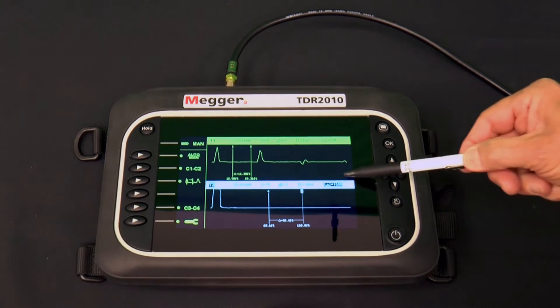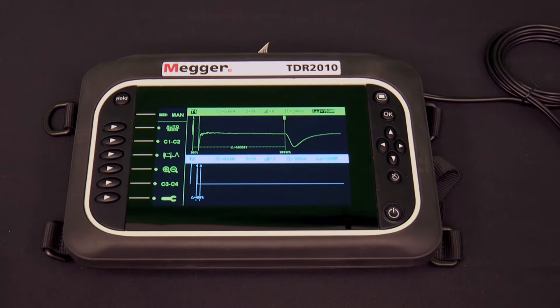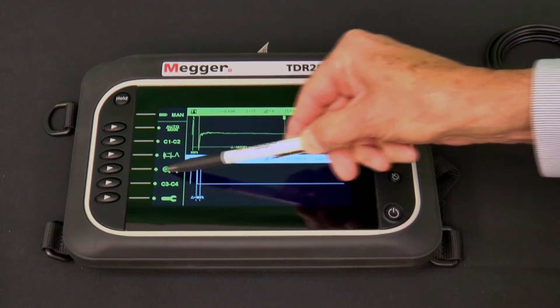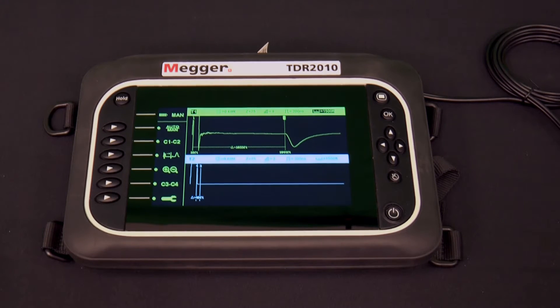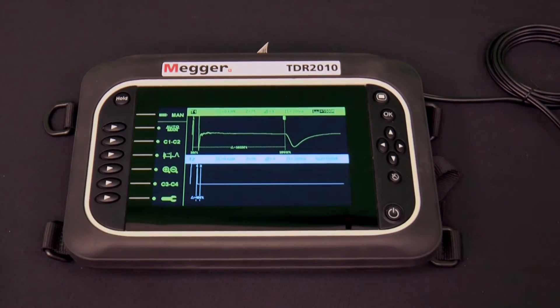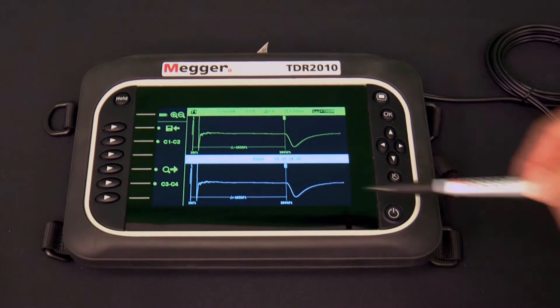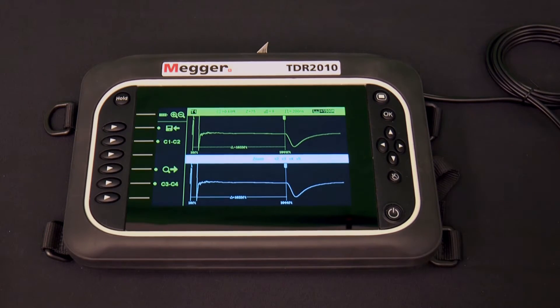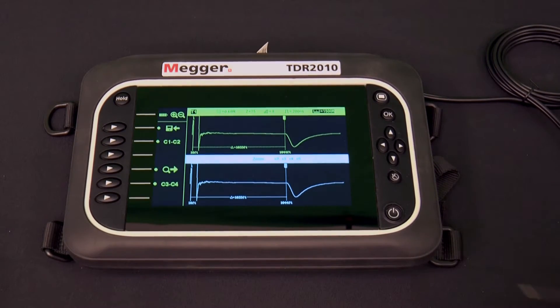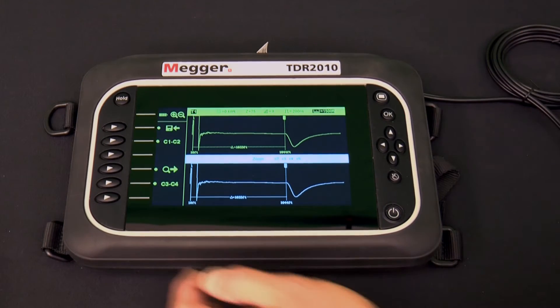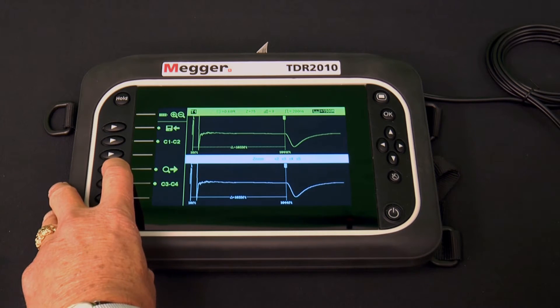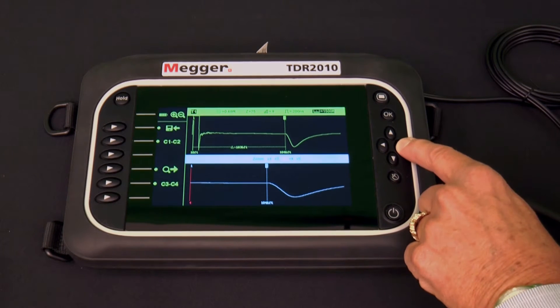The distance shown on the screen for that trace is now highlighted. Let's look now at the zoom function, which is controlled by the fourth soft key from the top — the one with the magnifying glass icons with plus and minus signs in them. The active trace is trace 1, and the active cursor of that trace is cursor 2. We have placed this cursor where we think the event is located. Press this zoom soft key and the inactive trace, trace 2, disappears, and in its place a duplicate of trace 1 appears. The zoom icon will change to a magnifying glass with a right-pointing arrow. Along the top of this duplicate is a list of magnification levels from which we can choose. Each time the zoom soft key is pressed, the level of magnification is changed and that level is highlighted. The cursor can be moved to adjust its position on the trace.